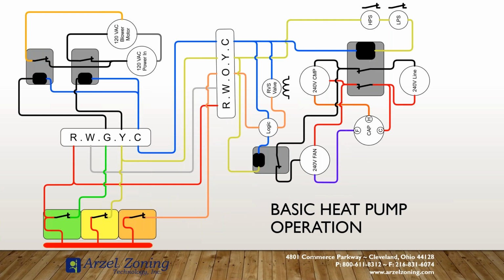A heat pump though adds an additional layer because there's a defrost board outside. And once upon a time, the defrost board would throw me for a loop, but then as I became more and more familiar with how low voltage circuits worked, the defrost board really isn't any big deal because it's all about a low voltage source controlling a high voltage source. So it's where's your power at? Once you've verified your power, you know that that part of the system is working. If it's not, then you found your problem.